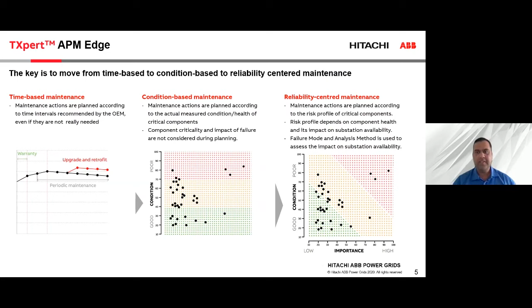Then we moved to condition-based maintenance, where we planned the maintenance of the device according to the measured health or condition of, say, the transformer. In that case, criticality and the impact of failure of the transformer were not considered. Now we are shifting to reliability-centered maintenance, where we account for the component criticality, the transformer criticality, and we develop the maintenance strategy based on how critical the transformer is to your network, what its health is, and what the impact of its failure to the network would be. And then we prioritize our maintenance.